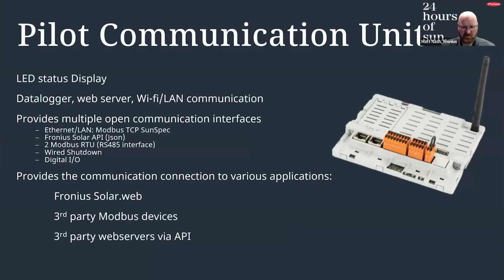And speaking of that pilot board, it's a data logger, web server, Wi-Fi and LAN communication device, as well as the brain of the inverter. So it offers multiple open communication interfaces. It is SunSpec Modbus certified. You can do API calls to the inverter in case you have your own app that you utilize for monitoring. It does offer 2 inputs for RS-485 Modbus RTU.